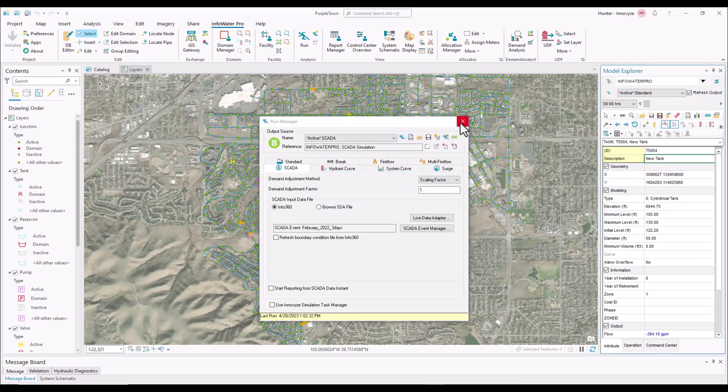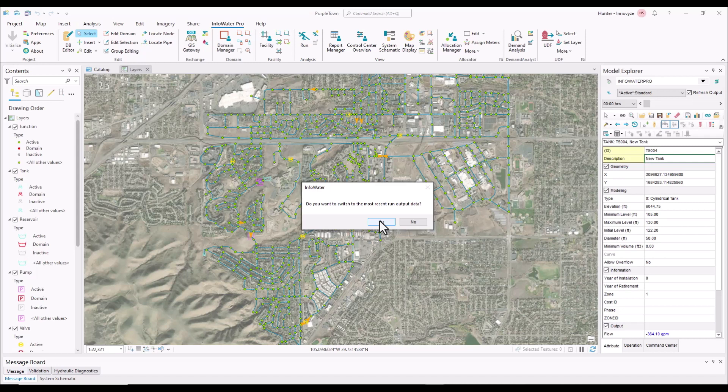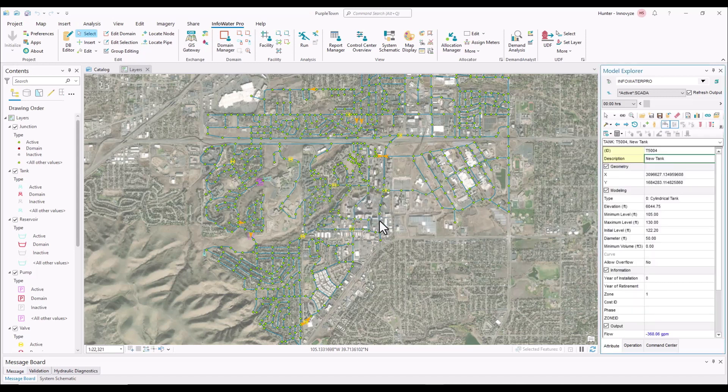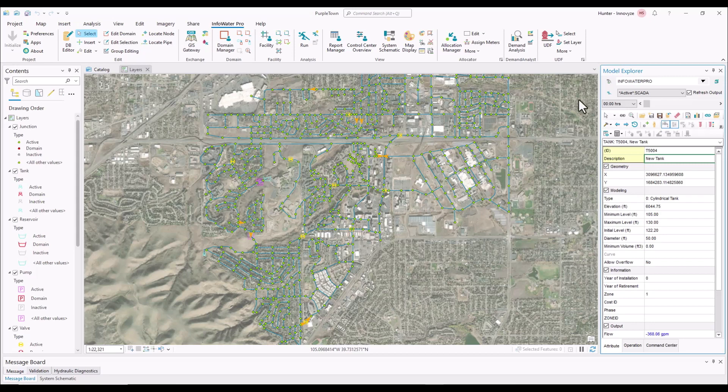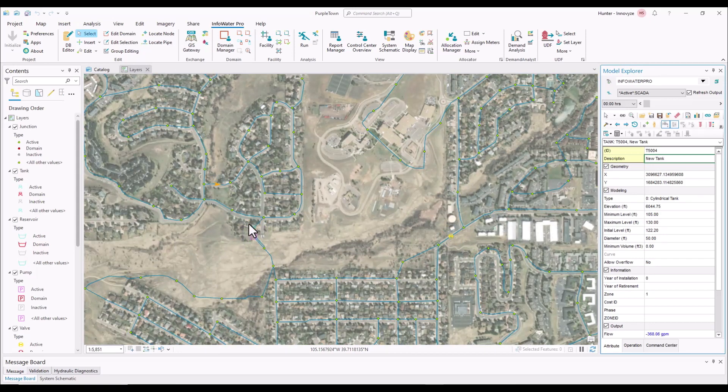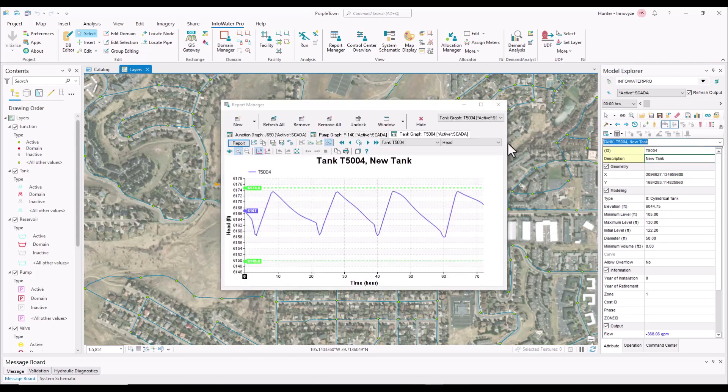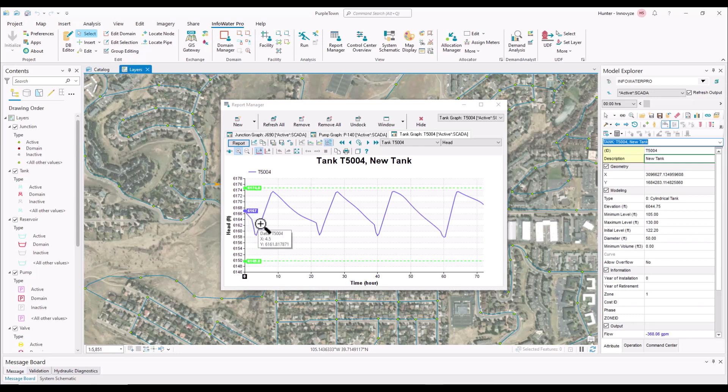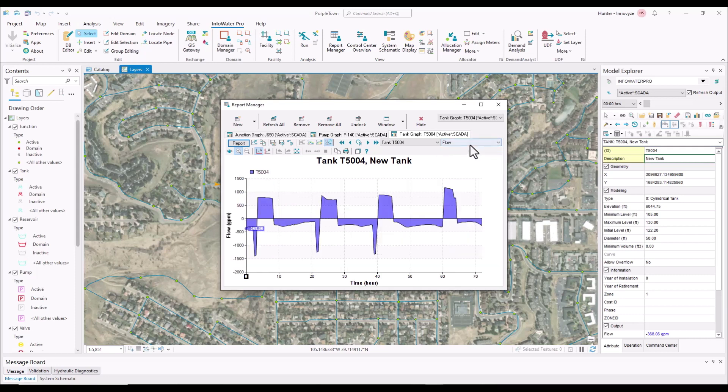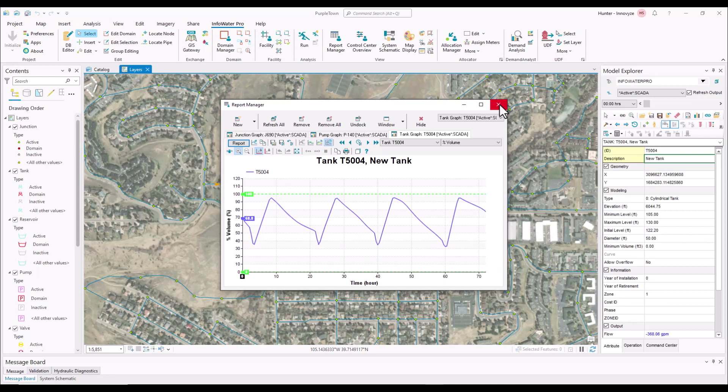And so what InfoWater Pro is doing is that it's running your hydraulic model, running a simulation using the SCADA data to influence it. And so we're going to switch to the SCADA run that we've just conducted, and now we can zoom into some of our assets and look at the graph. So now we can see these are the head results for our tank using that SCADA data. I could come through and look at the flow, percent volume, really you could open up multiple different assets to pull out that information. But now our model has been run using the live SCADA data.